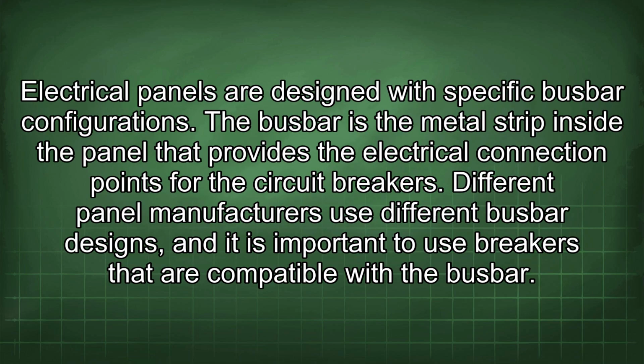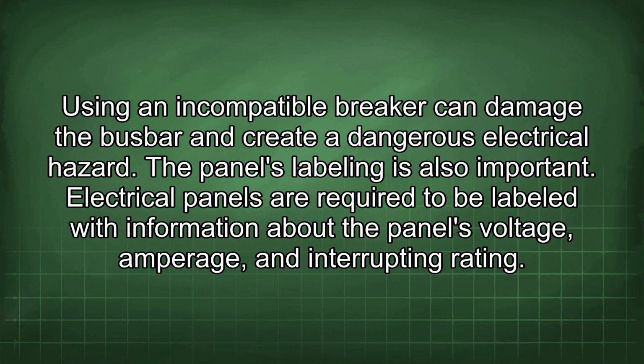The electrical panels are designed with specific busbar configurations. The busbar is the metal strip inside the panel that provides the electrical connection points for the circuit breakers. Different panel manufacturers use different busbar designs, and it is important to use breakers that are compatible with the busbar. Using an incompatible breaker can damage the busbar and create a dangerous electrical hazard.